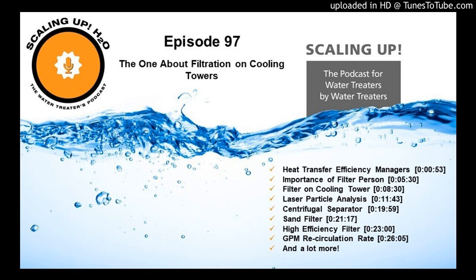Whenever you add a high-quality sand filter to a system, the particle loading in the sump drops by 80, 90%. So any customer that has a particle loading situation in the sump is going to find the sump quite clean after he puts a filter on it, because the source of the deposition is being taken away by a side stream filter.